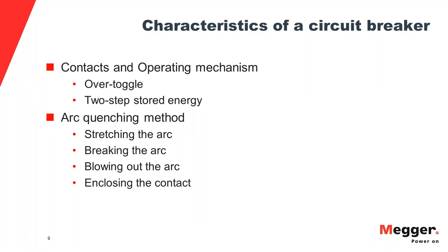Then you have the contacts and the operating mechanism. There are two main types of operating mechanism. There is the over toggle mechanism, which is what you typically see on MCBs or MCCBs. What it means is that there is a handle with which you can either open or close a breaker. When the handle goes over toggle, that is when it goes past the point of no return, then the contacts operate.